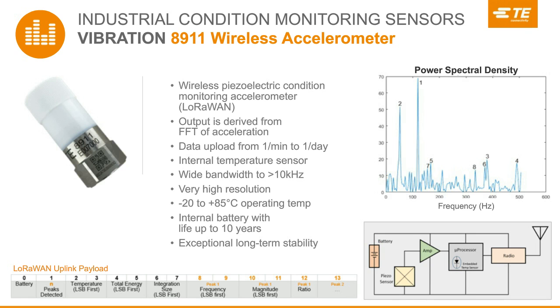We've talked about the need for broad bandwidth to detect signals for condition monitoring, but it's generally not practical to stream data continuously from a battery-powered device. The LoRaWAN protocol itself doesn't support high data rates, so instead, we've put some edge computing into this sensor. First, we compute the FFT of the time signal, just like we showed before. And then we extract key features from the FFT result. We identify the frequency, the magnitude of the strongest 8 peaks, along with the fraction of total energy that each peak represents. This compact summary of the data then forms the uplink payload, which is transmitted once per period.